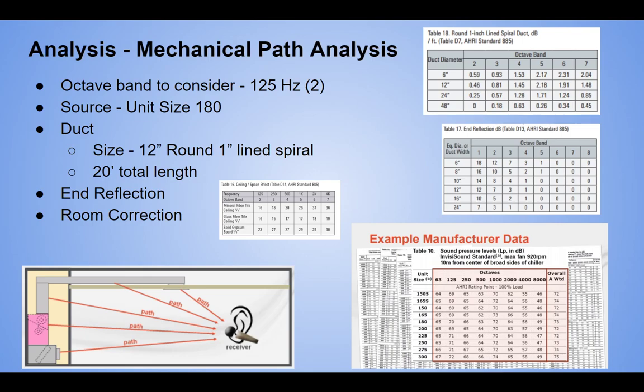I'll touch on at the end of this lecture some of the computer software that will run this and run all the bands and plot the NCs for us. But we want to know what that software is doing, so we're going to look at one octave band. We've got a source that is identified to us. We're using a source that wouldn't necessarily be used, but it's good for this scenario. We're going to overlook that it's actually a chiller, but the reason for doing this is the charts are similar and it matches the sound pressure that we want to get into. Then we've got a duct size of 12 inch, and that has a one inch lined spiral, spiral duct, 20 feet of that. We're going to look at end reflection and then room correction.